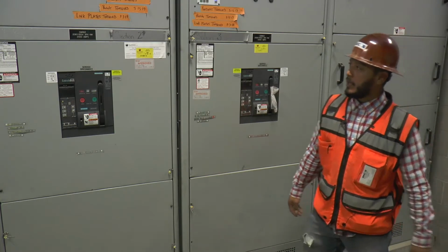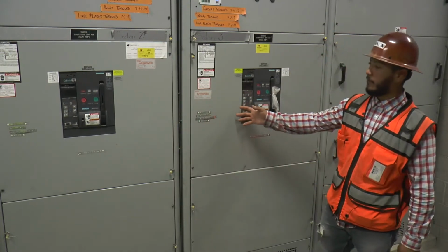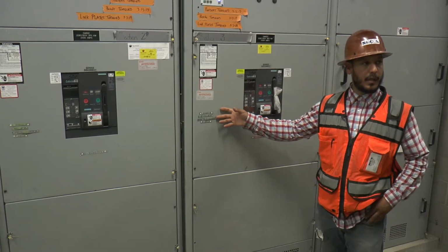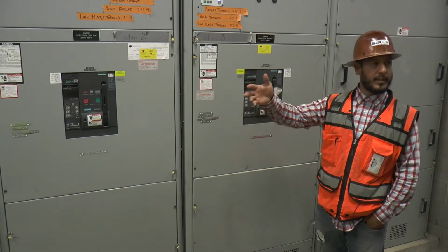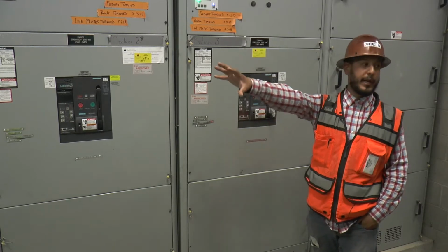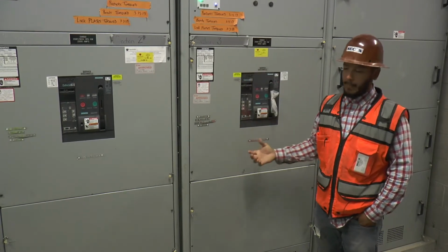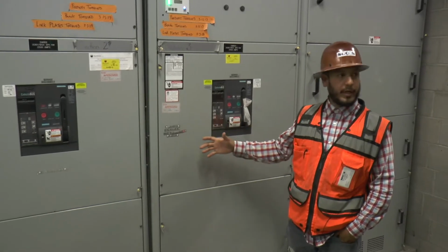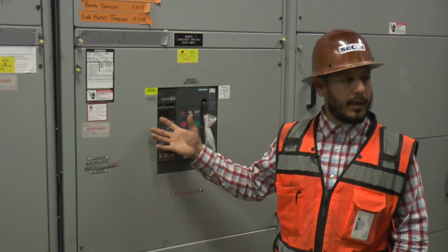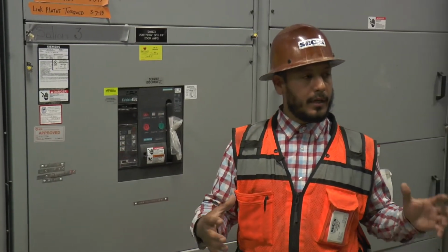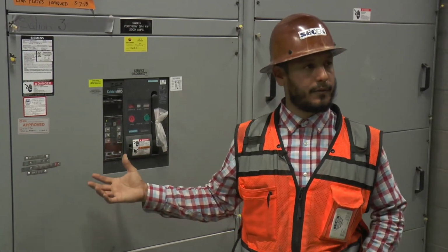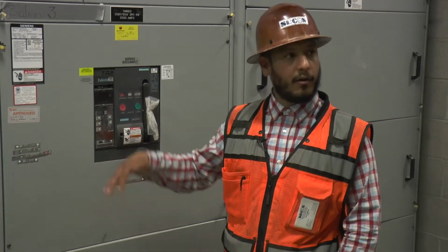All right, now this is switchboard 2 and switchboard 3, both identical, 2500 amp services coming in from APS from their step down transformer 120/208. So these are distributed from 480 already outside. This is going to be cable transfer to a tap box that is located in the front lobby, and from there we'll transfer to Siemens busway to distribute all the power for all the meter sections for all the tenant rooms from 8 all the way up to 30.